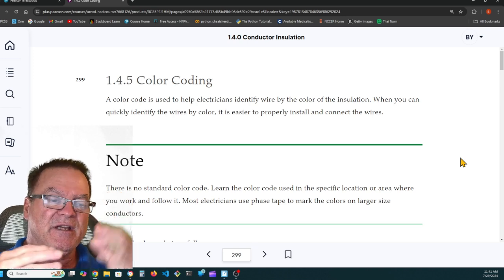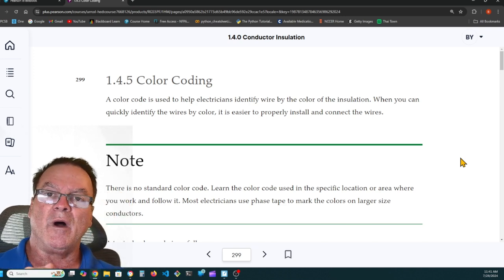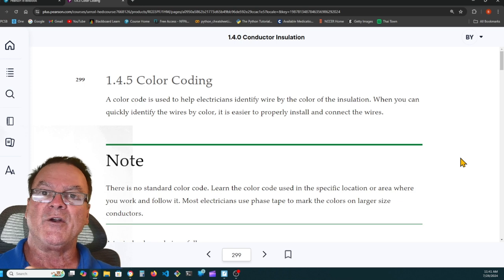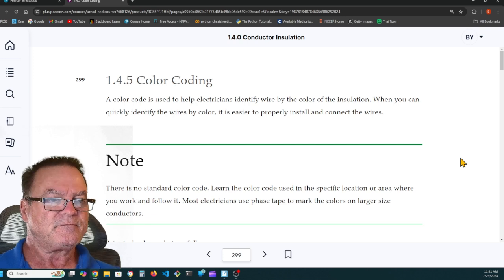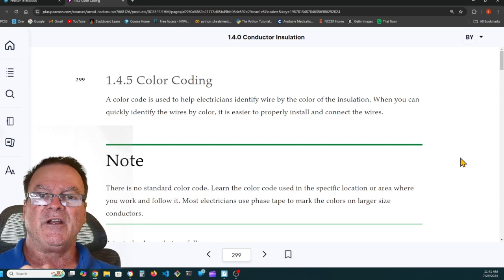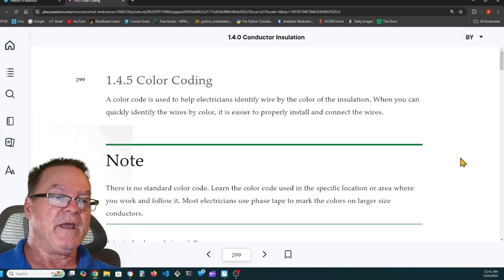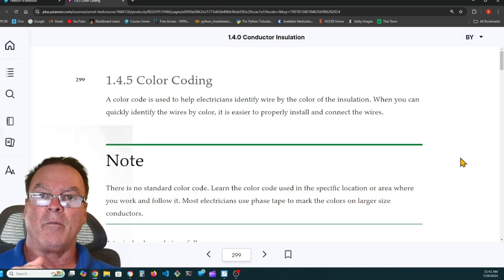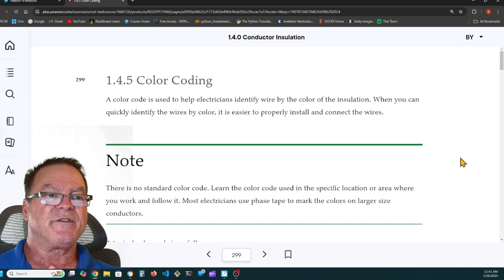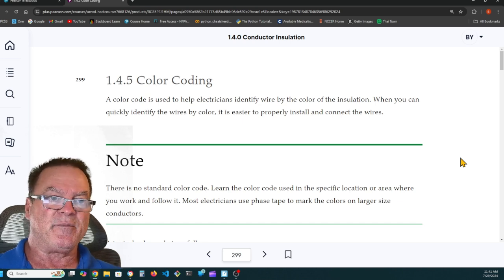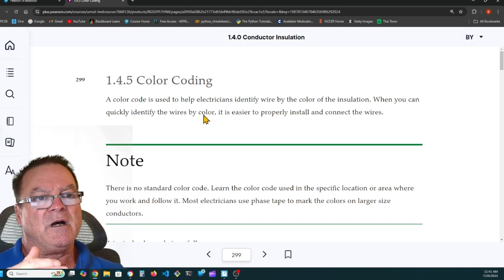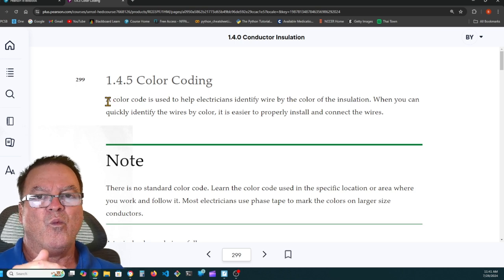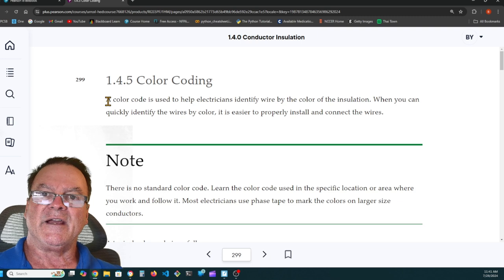It does stipulate that neutral wires, grounded wires, will be white or gray, or any color other than green with a white stripe or 3 white stripes. The grounding conductor has to be green or bare or green with a continuous yellow stripe. So it has stipulated green and white and gray.